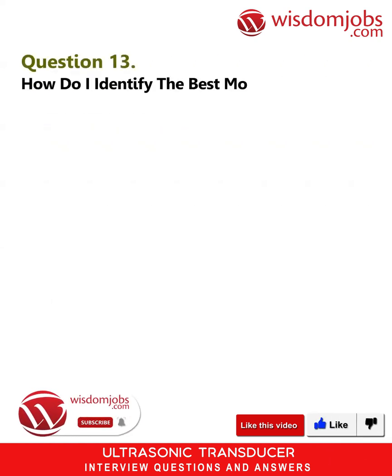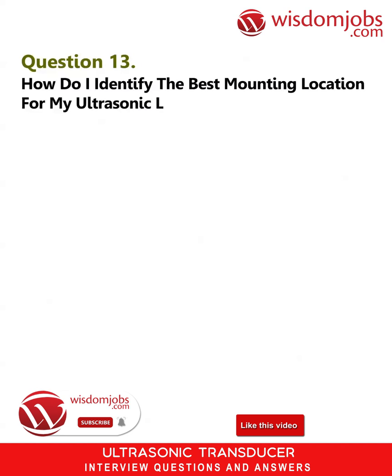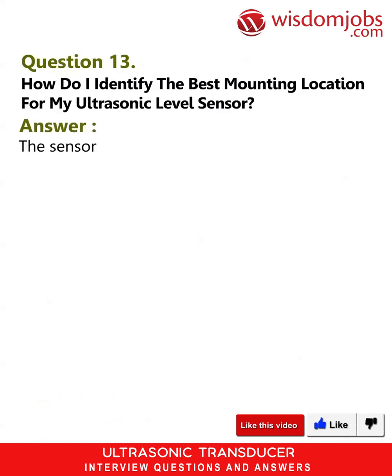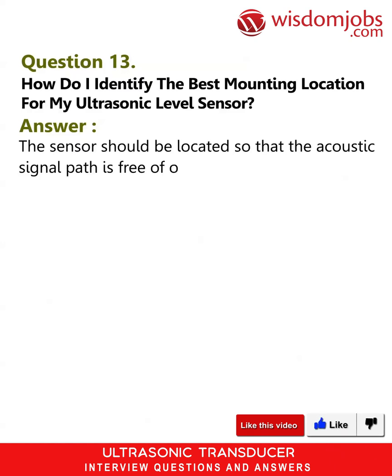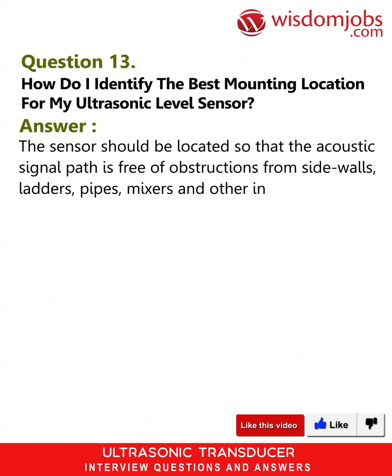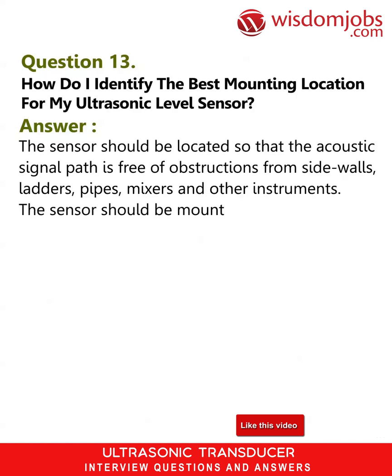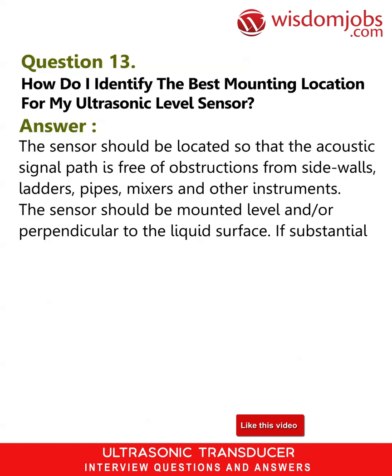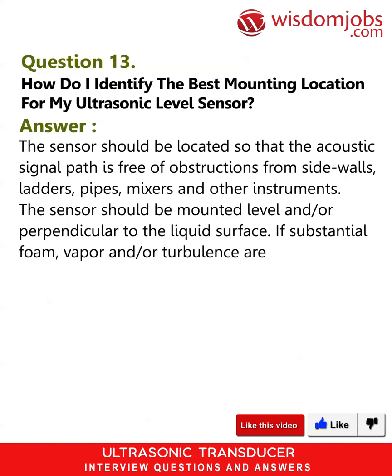Question 13. How do I identify the best mounting location for my ultrasonic level sensor? Answer. The sensor should be located so that the acoustic signal path is free of obstructions from sidewalls, ladders, pipes, mixers and other instruments. The sensor should be mounted level and/or perpendicular to the liquid surface. If substantial foam, vapor and/or turbulence are present, install the sensor in a standpipe.